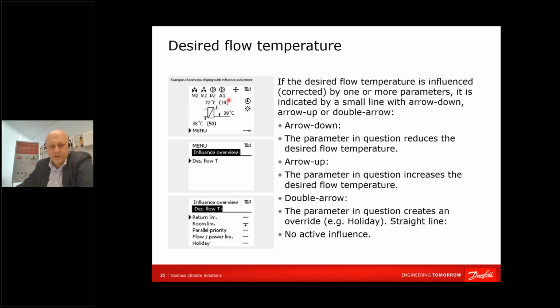You see in the parentheses that your target is 10 degrees now, and in fact ECL is making, as we see here, 72. Limitation of return temperature is set to 50, but we have 38. Then we have that strange symbol. Then we go to the menu, to desired flow temperature, and look inside to see what is happening. Aha, we see the arrow pointing down, meaning that our room temperature influence is telling us to go down to the return temperature. So that's the answer to what is going on. And there are many more parameters in there, so you will discover what is influencing your supply temperature, and why it is not what it should be.